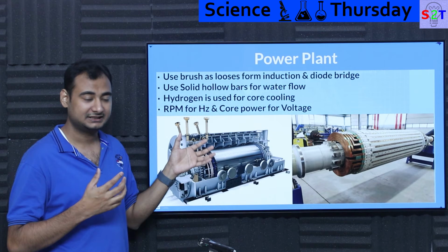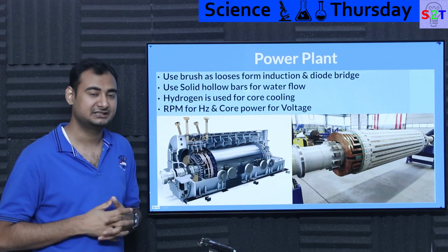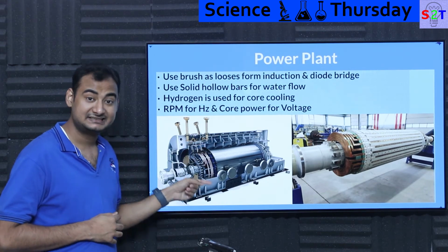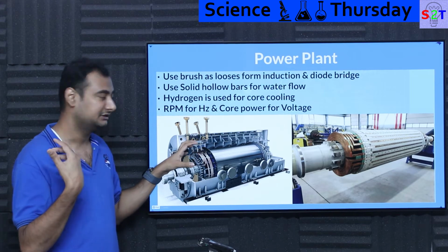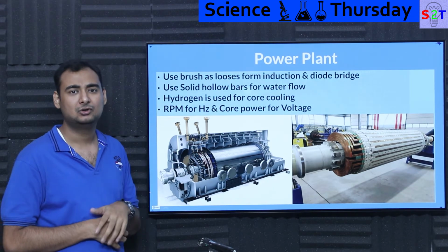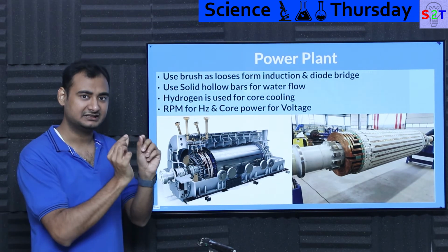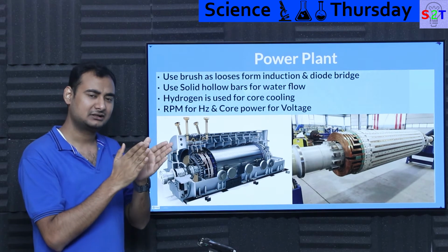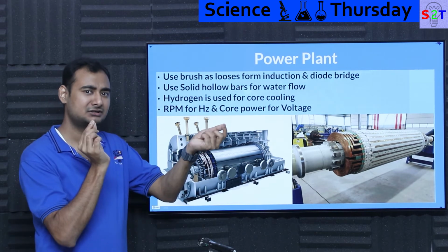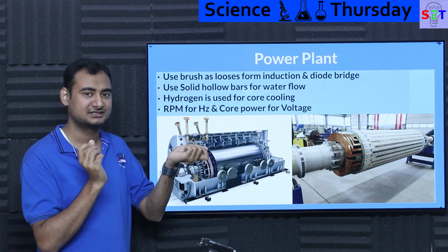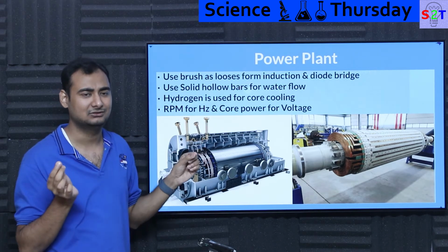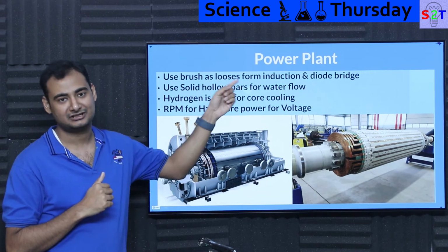Then we come to how the heck these puppies are operated. What's the unique thing about them? Well, generally on the stator side, basically the things that are giving you the energy, they have hollow tubes in them. Basically the conductor is hollow tubes. At lower megawatts, as in like 4 or 5, they are rods, and at higher megawatts, as in like 100 megawatts, 600 megawatts, they are hollow tubes. Now why the heck is it hollow? Well, it is hollow so water can flow through it.